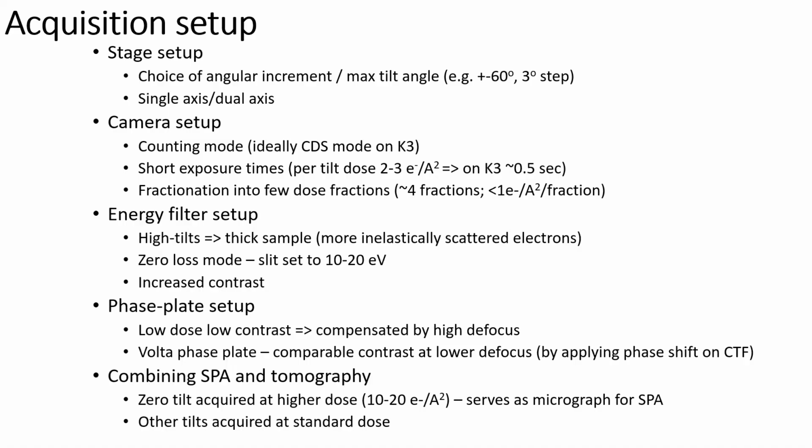Now, the acquisition setup itself, well, we know how the acquisition works. We need to choose our angular increment, the maximum tilt angle. That means how many tilts we are going to acquire. Therefore, how we need to set up our dose per tilt.